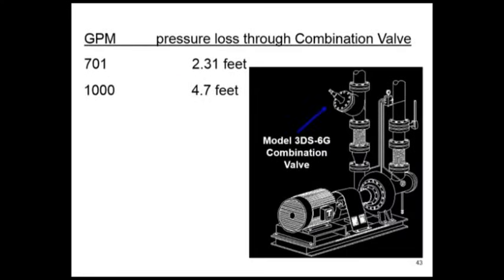I just figured out that at my 1,000 GPM, my pressure drops 4.7 feet. Now I could go ahead and keep that same setting, not change the setting I got on my system sizer, and add in these other flow rates. Now remember, I told you that if I double the flow rate, my pressure drop should be 4 times. So let's just see now.